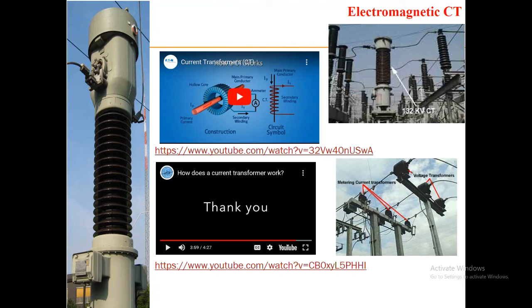The secondary winding normally consists of few turns up to 500, and the bandwidth of such transformer may be typically 40 hertz to 1 megahertz for a peak current of 1 kiloampere with output voltage across the secondary between 0.5 to 5 volt when terminated by 50 ohms.